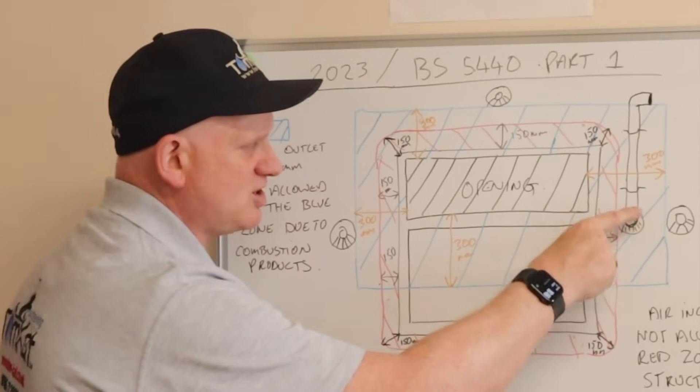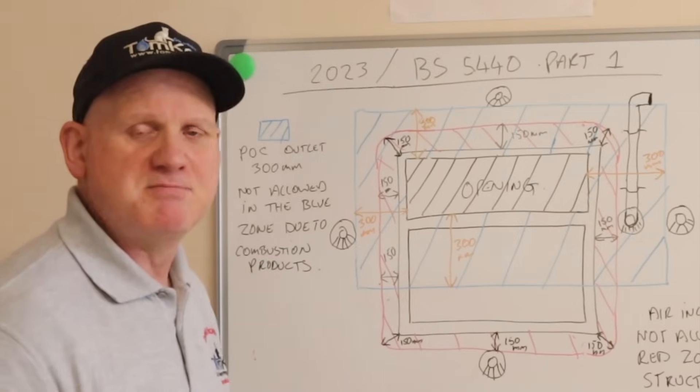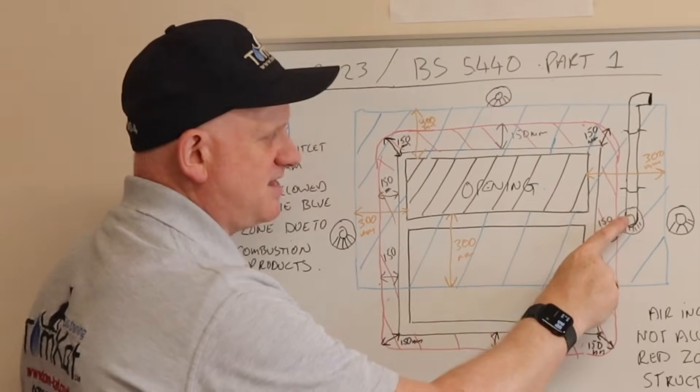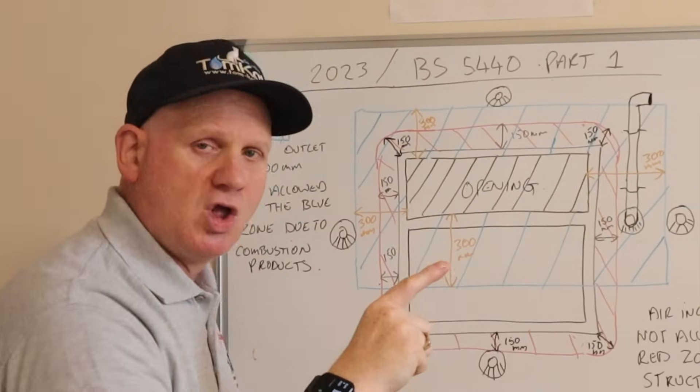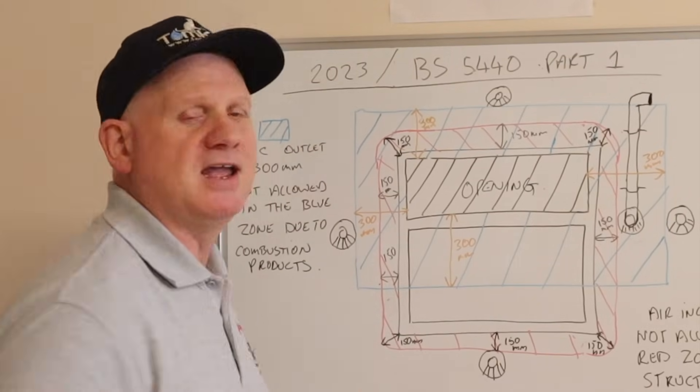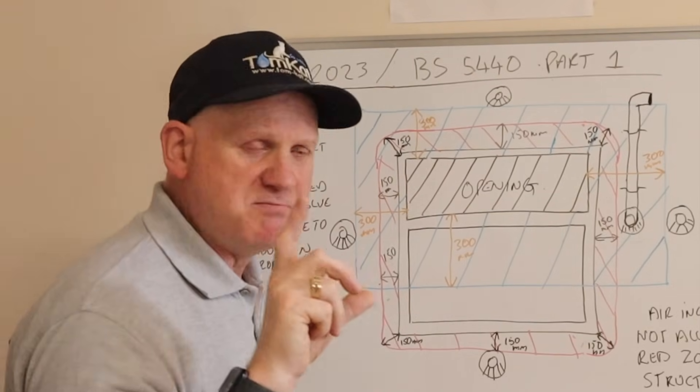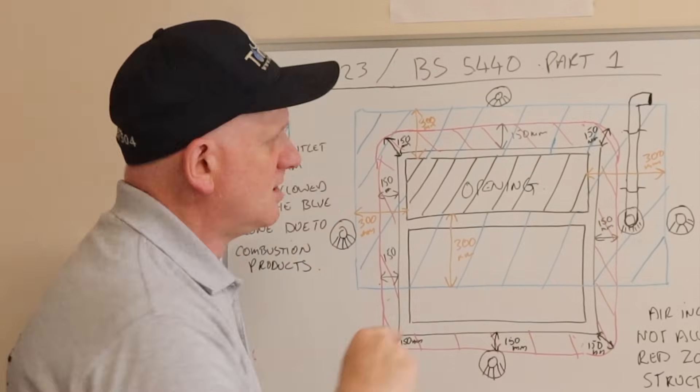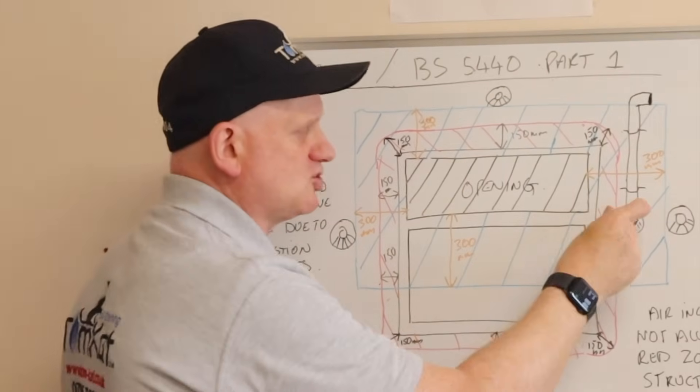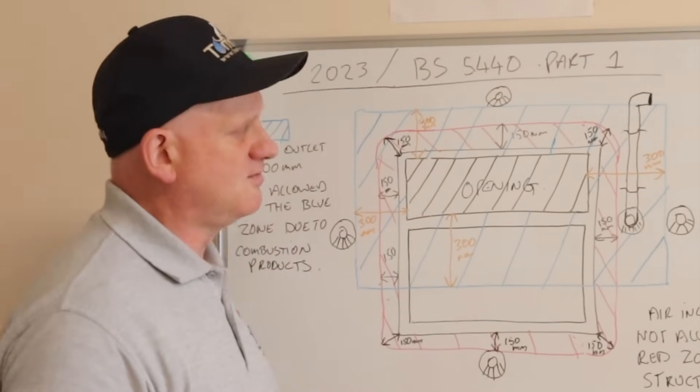So if we were going to install a flue here, and we were more than 150mm away from the frame, we can use a plume management kit. Now this plume management kit then will have to terminate more than 300mm away from the opening in the building, so outside the blue zone. It also has to have a minimum of 500mm.